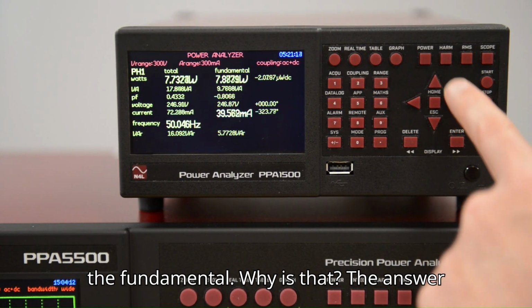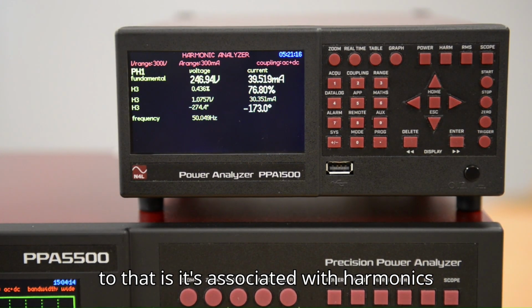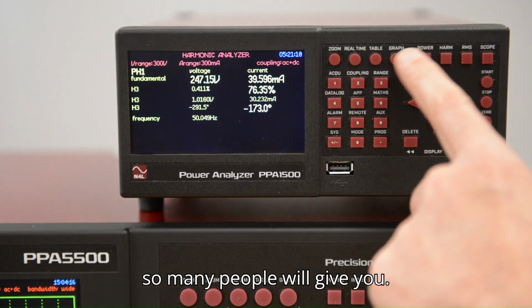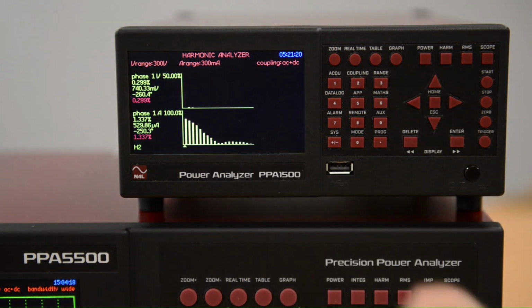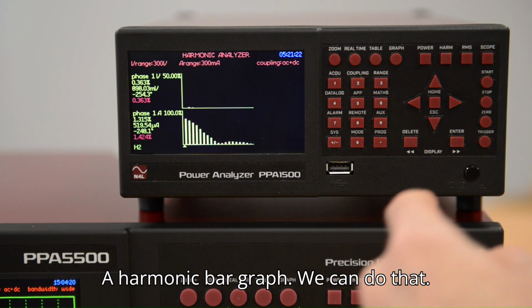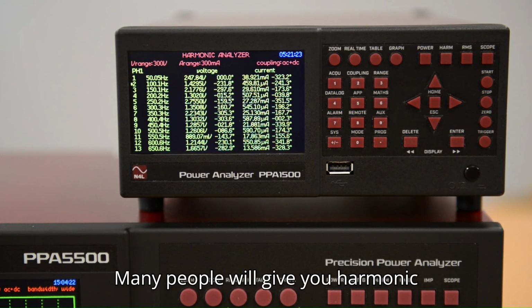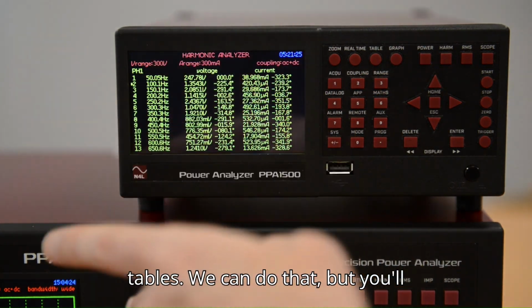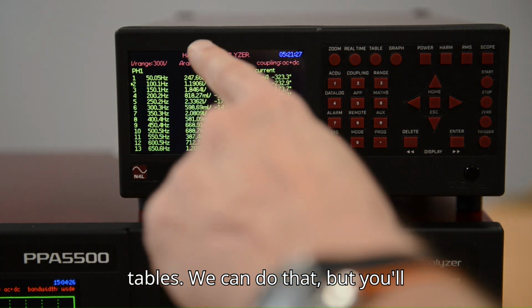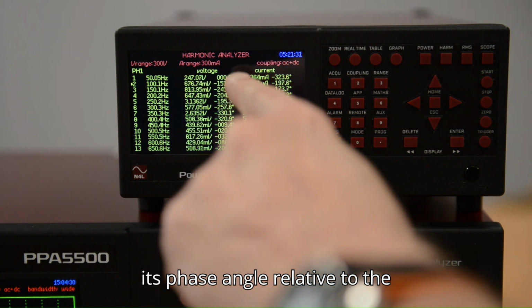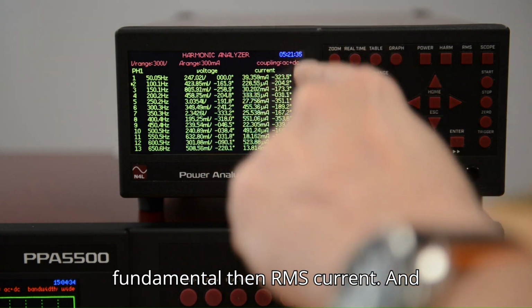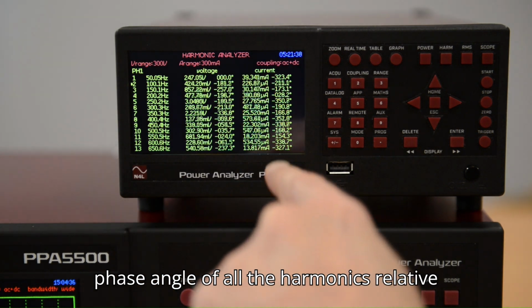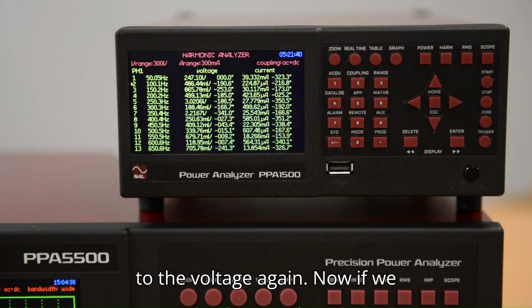The answer to that is it's associated with harmonics. So many people will give you a harmonic bar graph. We can do that. Many people will give you harmonic tables. We can do that. But you'll notice that we have RMS voltage and its phase angle relative to the fundamental, then RMS current and phase angle of all the harmonics relative to the voltage again.